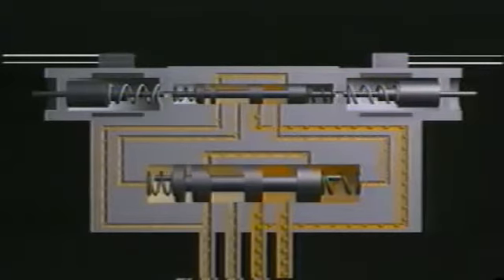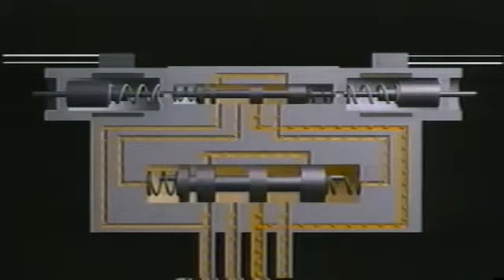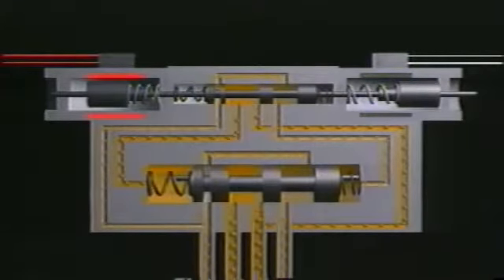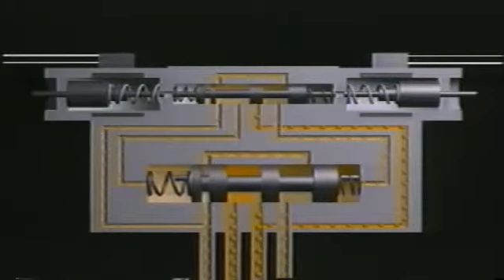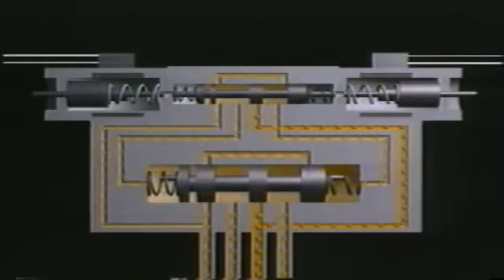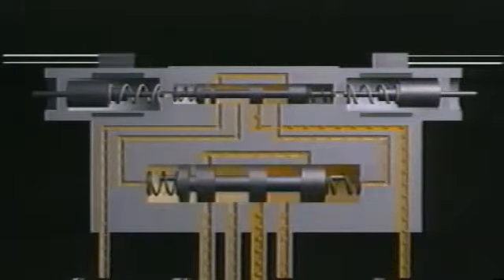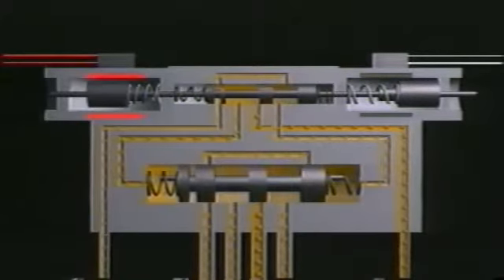There are two types of pilot control. The pilot valve switches the power valve either with the aid of the normal working pressure of the hydraulic oil, or with a separate lower pressure that is supplied via a different port. The latter method results in smoother switching of the directional control valve.